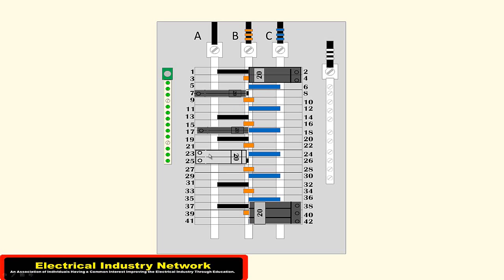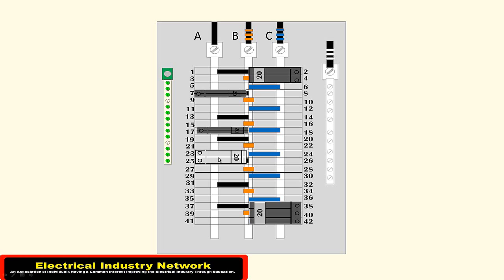Now this two-pole here can be a 120/240 because it's using the A phase and the C phase. So C to ground is 120, A to ground is 120. So you're good with using that breaker there.